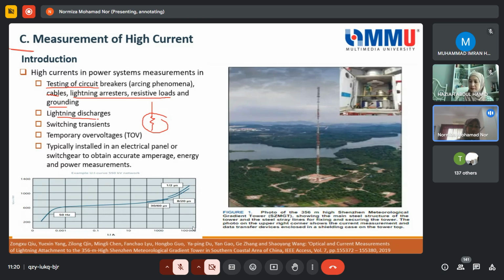Okay, so lightning discharges, switching transients and temporary overvoltages, typically installed in an electrical panel or switchgear, where this is actually installed. They also put this current measurement in the substation to obtain accurate readings in terms of energy and power measurement. This is an example of the UI curve for a 550 kV network. So they still need this current measurement.